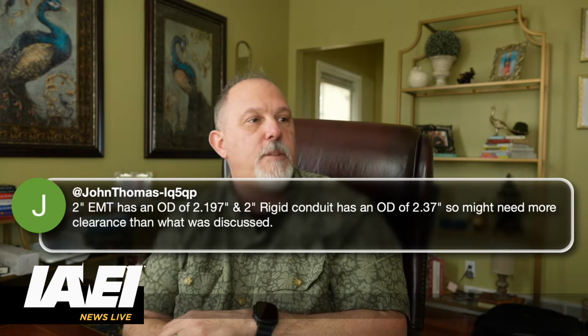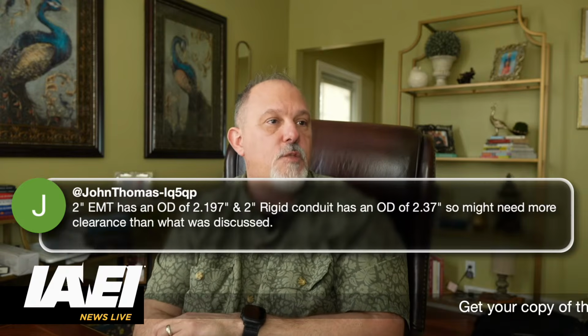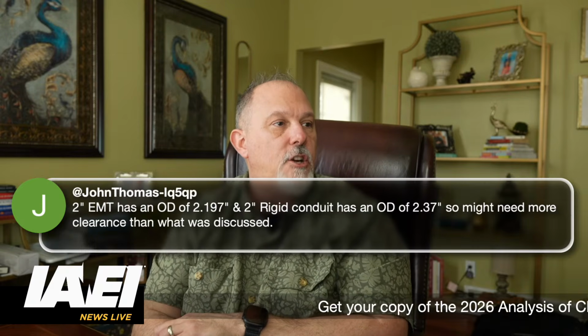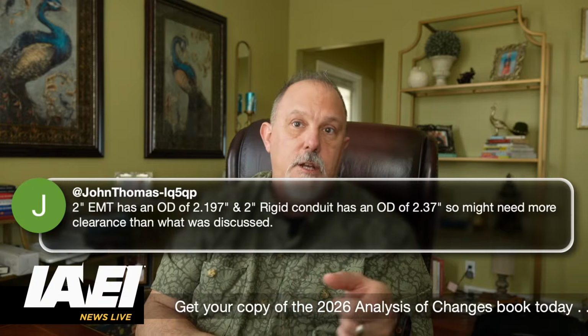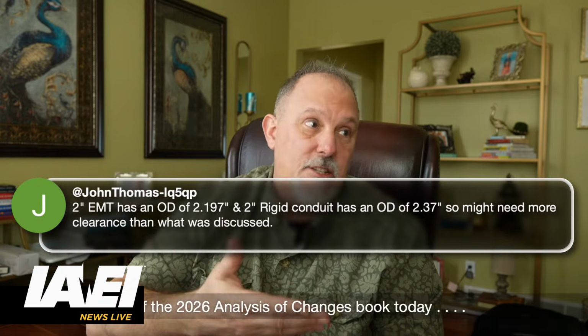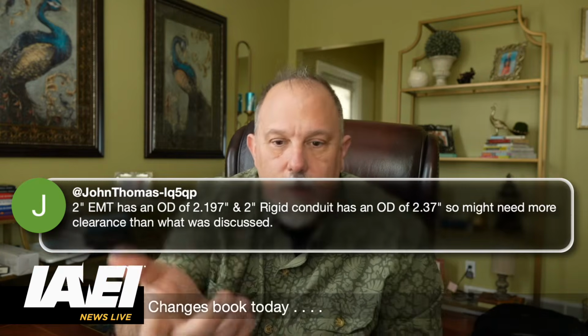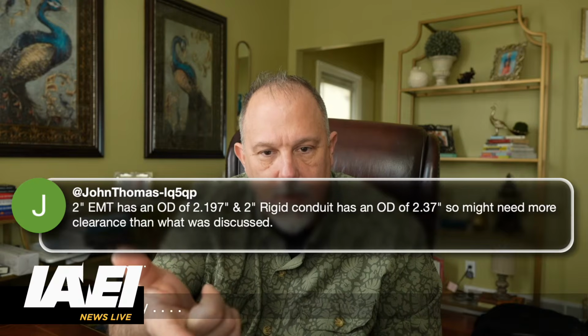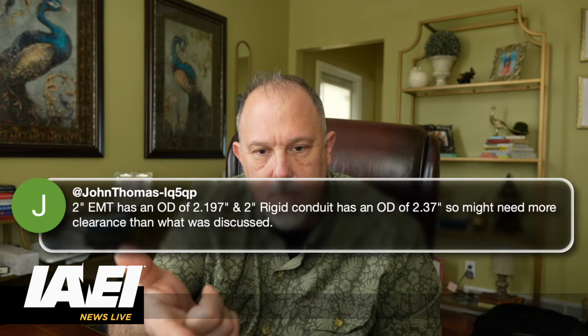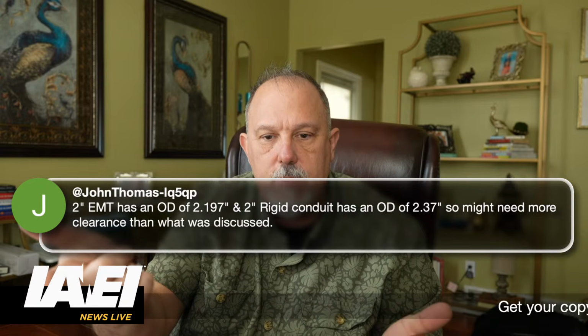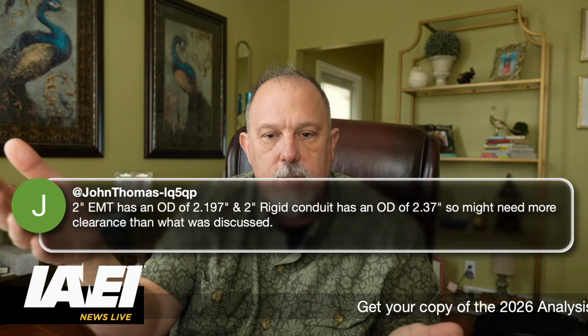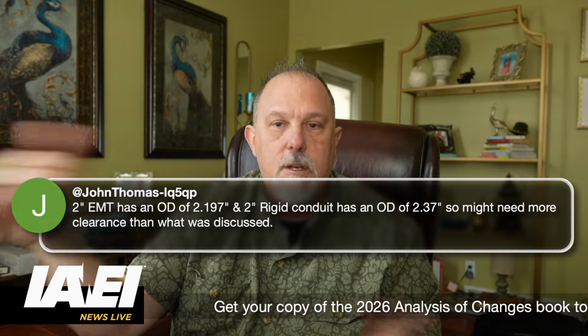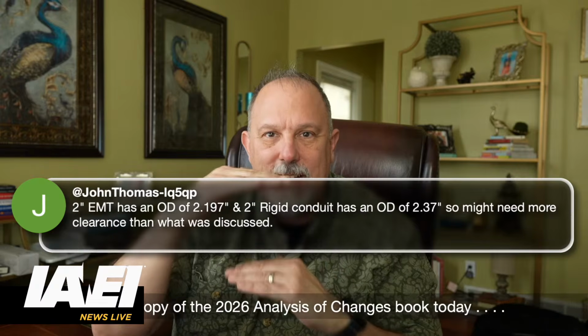Wiring methods and materials shall be permitted in concealed locations where encased in concrete not less than 2 inches. So 3 inches is not less than 2 inches thick. So I could take that 2.37 outer diameter rigid metal conduit, I could make my concrete 2.5 inches, just cover the top and bottom, and say it's encased.